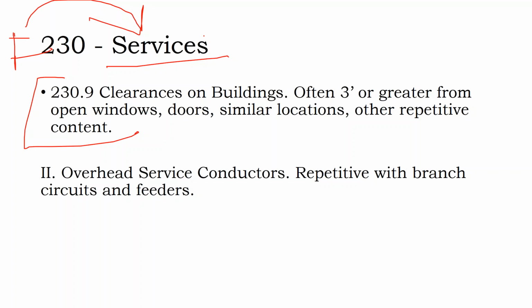And, you know, again, we have to stay 3 feet away from open windows, doors, similar locations on the outside of the building, except up at the top of the building where you're allowed to sneak alongside the dormer. So you could actually be dinged on an inspection if you're doing an exterior conduit run and you're saying, well, I'm doing an exterior conduit run so it's safer and it's also easier and cheaper. I'm not a fan of exterior conduit runs. I like doing interior conduit runs.